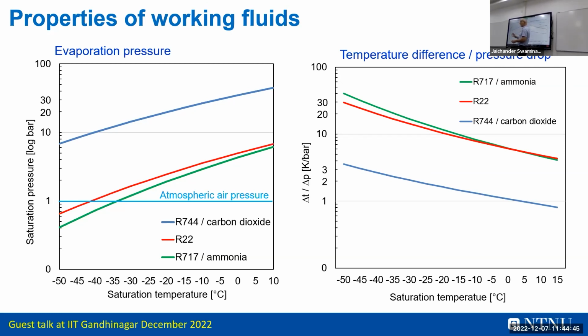On the other hand, the density is also very high, so the pipe size gets very small. So weight-wise, the weight of a system is quite comparable, actually. So there is not much penalty on that. What is important to understand, when we go to low temperature refrigeration, freezing of foodstuff, with CO2, we can go down to -50 and we still have 5 bar in the system, which is good. Ammonia at around -35 is at ambient pressure. And then if we go lower, the challenges with leaks go the wrong side, and moisture coming in and all this trouble. So at very low ambient, low freezing temperatures, CO2 is the best choice. I will show some examples later. Fish freezing and all this stuff on fishing vessels is done by CO2, because we can go down to -50.